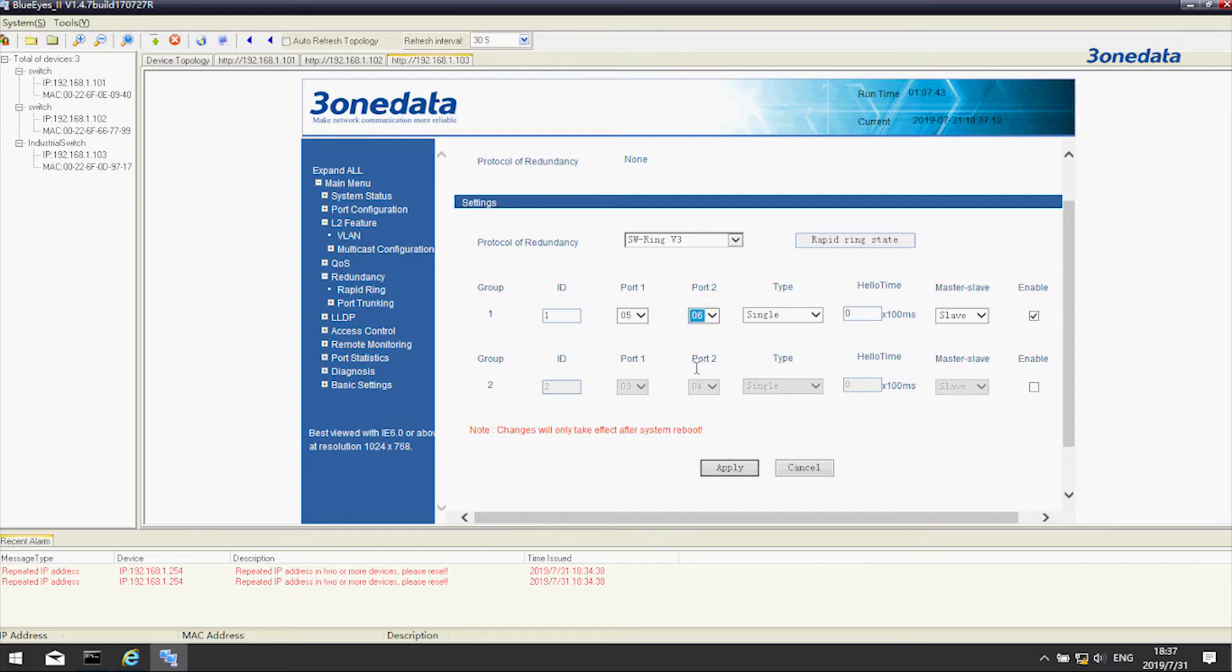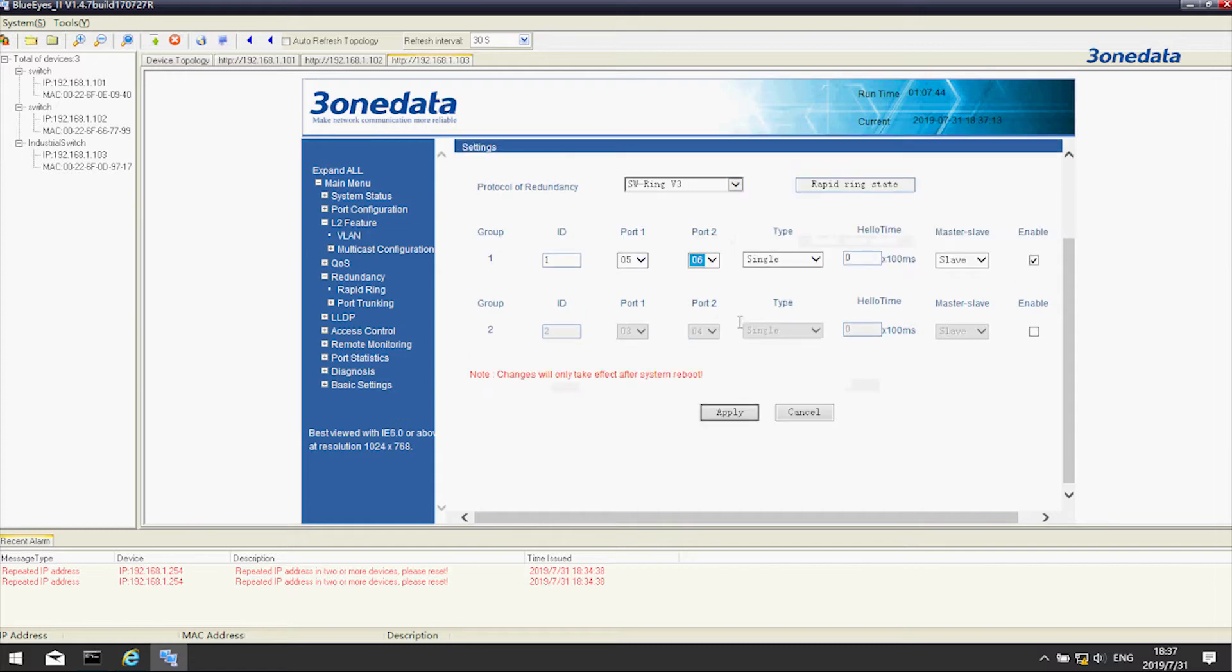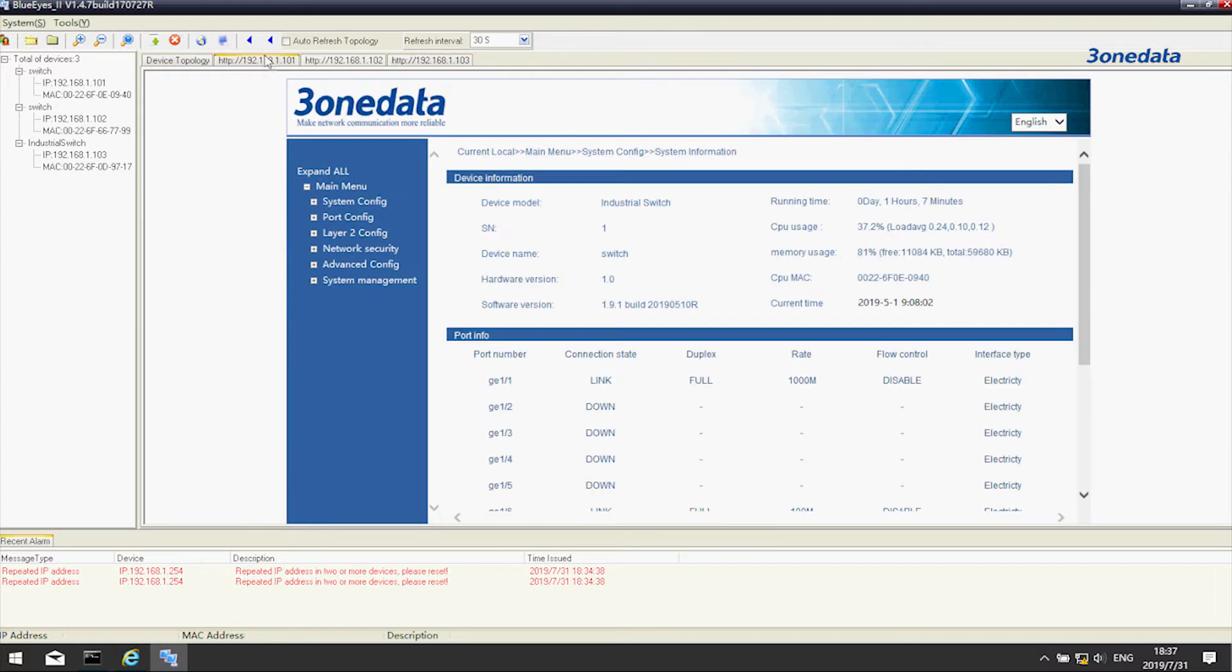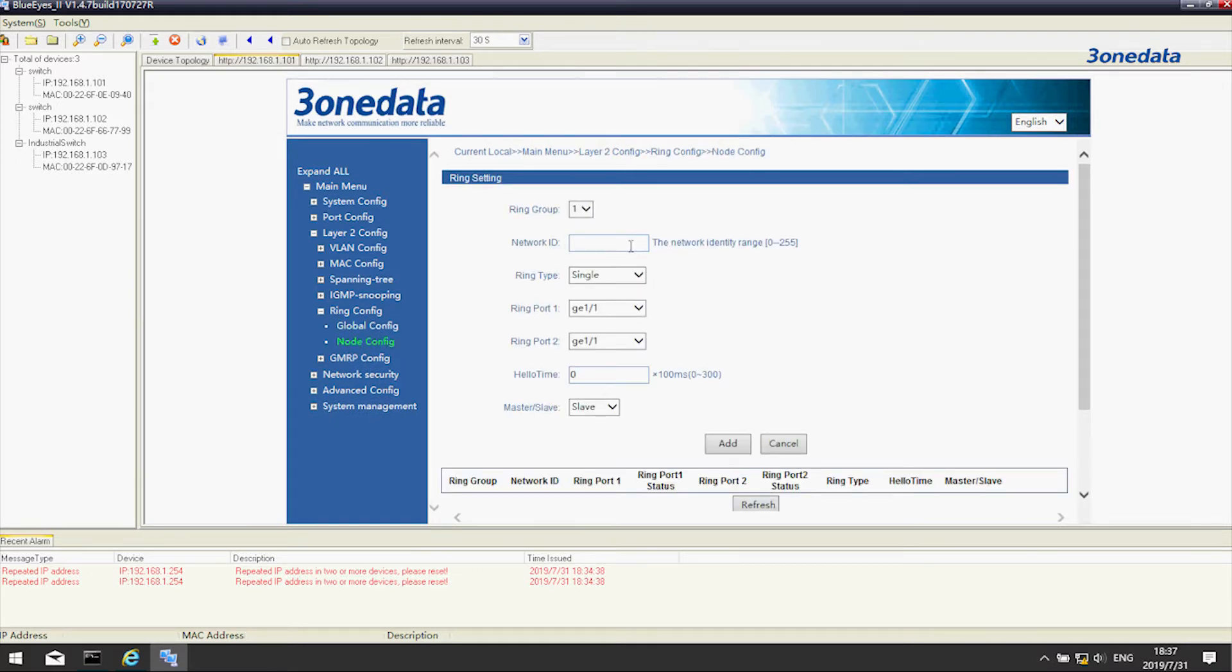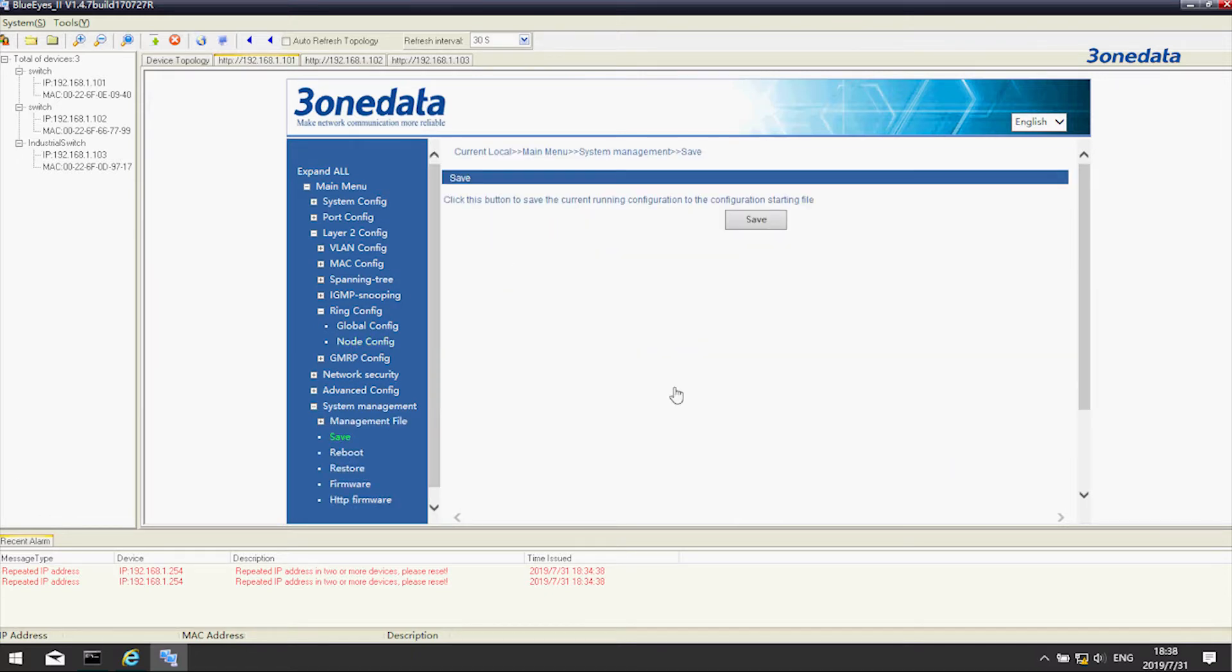Activate ring protocol, select the corresponding port and single ring. All ring IDs in a ring group should be the same. Click setting after configuration. The setting will take effect after rebooting the device.